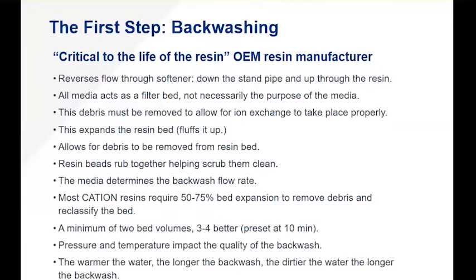One thing about backwash: the warmer the water, the longer the backwash you need. The dirtier the water, the longer the backwash. Everything in water treatment is a contextual discussion — it's all about the source water you're dealing with. When you hit around 80 degrees incoming water temperature — and this does happen in the southern United States quite often and definitely in Latin and Central America — you need to extend your backwash times. Why? Because the water isn't as dense. When you warm it up, it doesn't have the ability to lift that resin as easily, so we need to extend the backwash to get it clean.